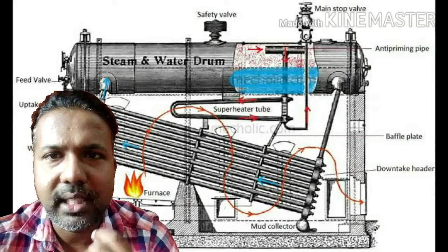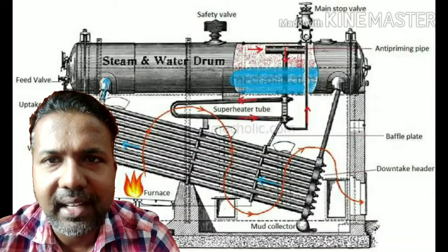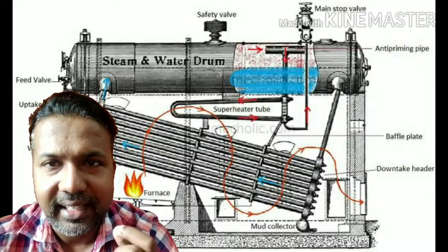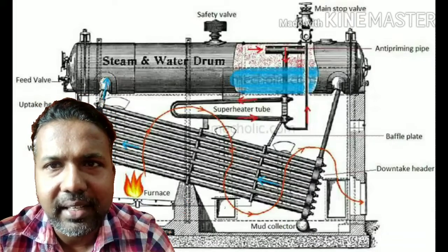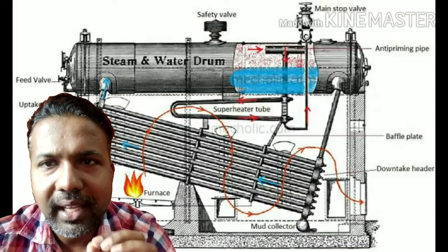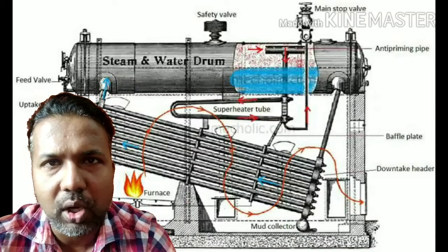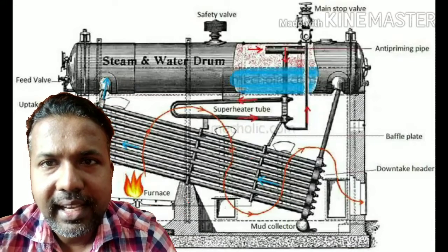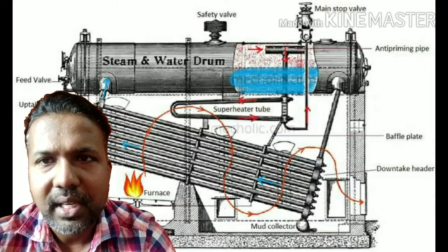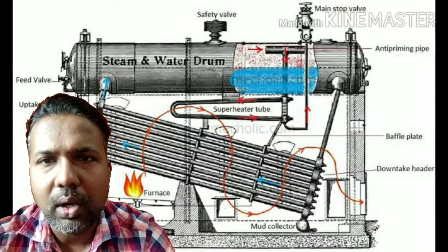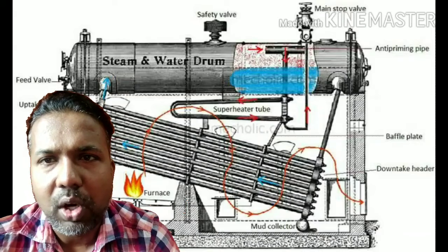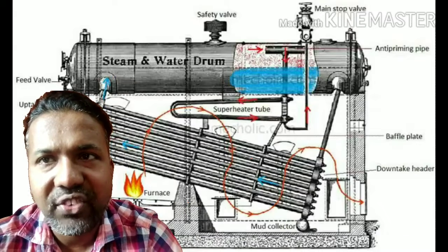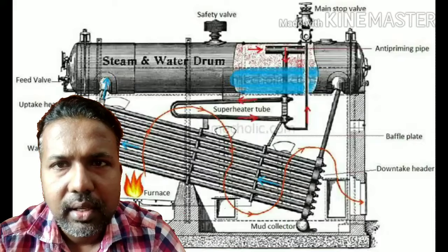Inspection of this type of boiler can be done anytime during its working. But it has some disadvantages too. High maintenance cost, and it is not very suitable for impure and sedimentary water. In the case of impure and sedimentary water, scale may deposit in the tubes and this leads to overheating and bursting of the tubes. That's why water treatment is a must before feeding into the boiler. Thank you.